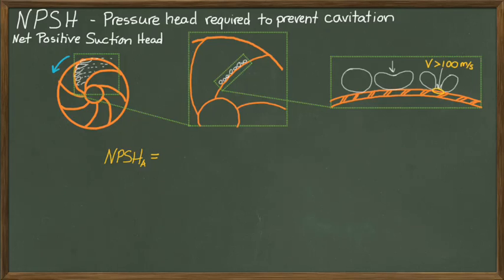It is calculated using the potential energy between the reservoir and the pump elevation. Written this way, you can see that if the pump is higher than the reservoir, then there is a negative potential energy that the pump must overcome. While if the pump is below the reservoir, then the potential energy is helping our NPSHA calculation. Next, we add in the effect of atmospheric pressure. This is a function of the elevation of the pump above sea level.